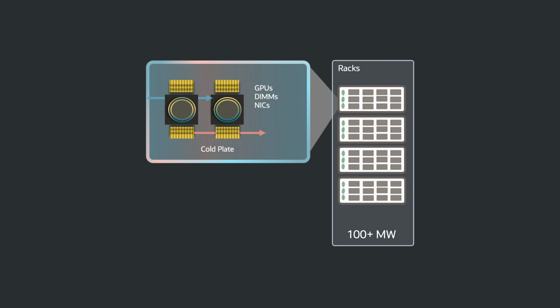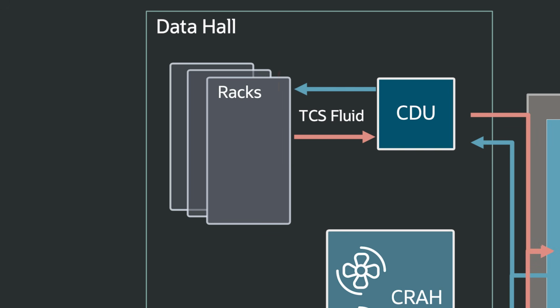So there are 2 loops for liquid cooling. One is called the facility water loop. Another one is called the TCS, or the technology cooling system loop. The technology cooling system loop is the one that touches the GPUs. So there is a cold plate on top of the GPUs. There are micro channels in the cold plate. So the liquid goes through the micro channels, absorbs the heat and brings it back to the CDU, or the coolant distribution unit. That's where the heat is transferred.